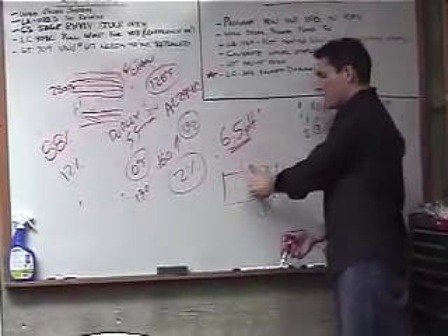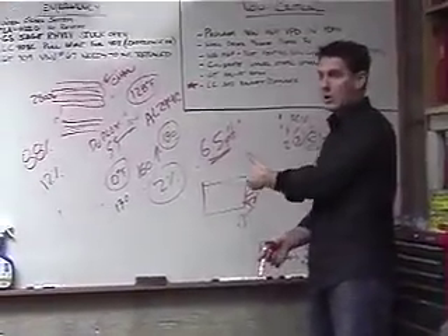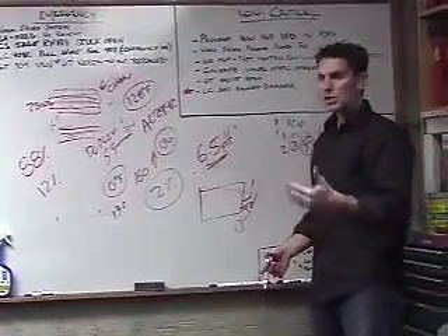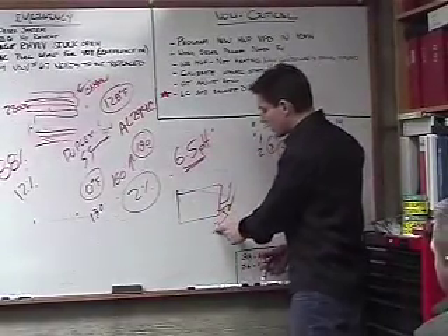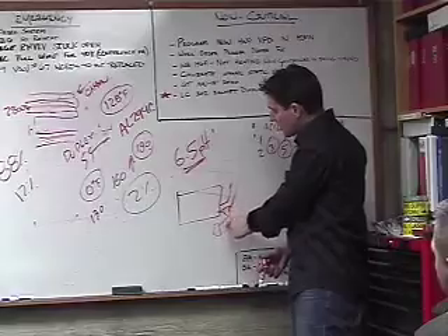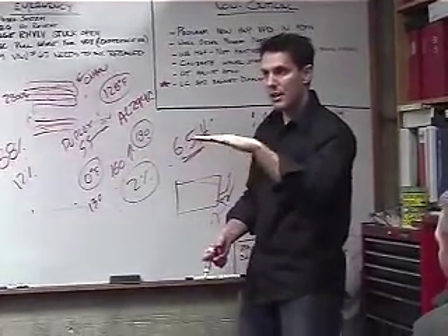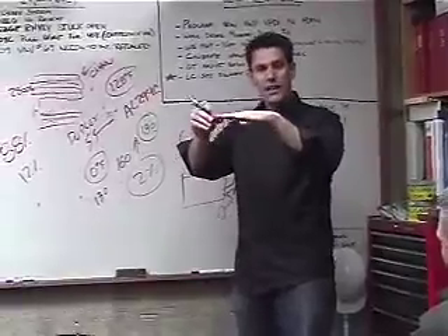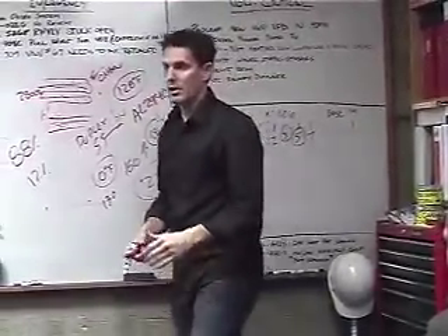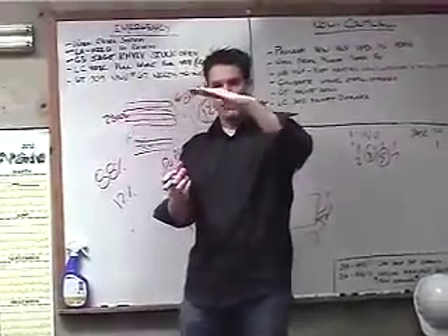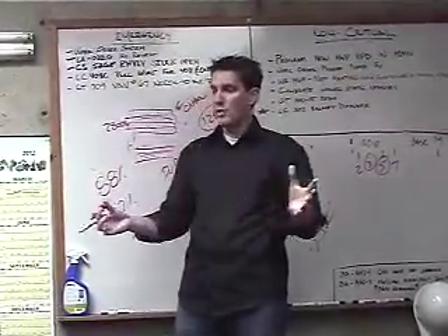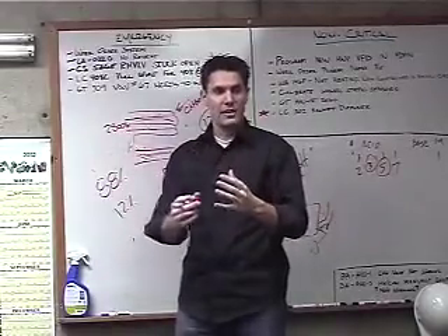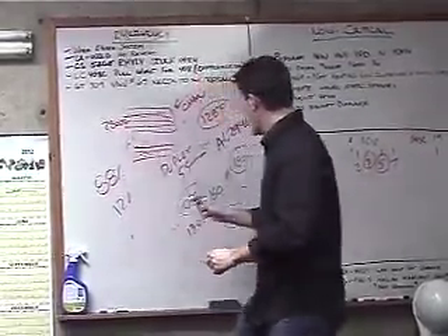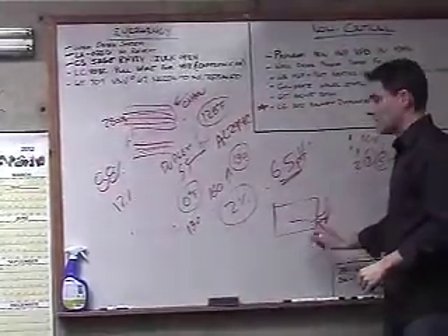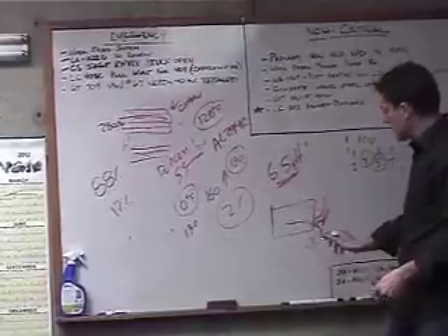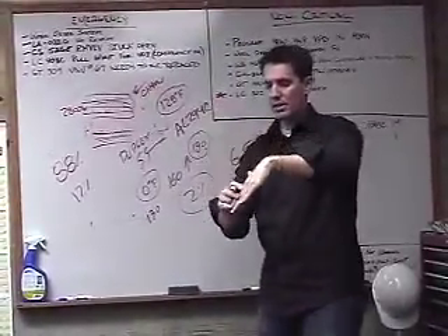By doing that, what are we now blowing into the room? Yeah, we're blowing products of combustion into the room, potentially killing somebody. So to protect you guys, we have this little condensate trap. All this liquid goes through this condensate trap. It's got a little float level in there. That float will detect the level of the water. If, say you shut the boilers down for the summer, that water will start to evaporate and go away, and so the float drops. Eventually, without that float inside, you have no water when you turn the boilers on until you start building up condensate. You're going to be blowing products of combustion into the room. Why would the products of combustion want to go all the way up the stack when some of it could just be dumping into the room? It's very dangerous. So this trap, this level, will detect if water starts to leak out. It will drop.